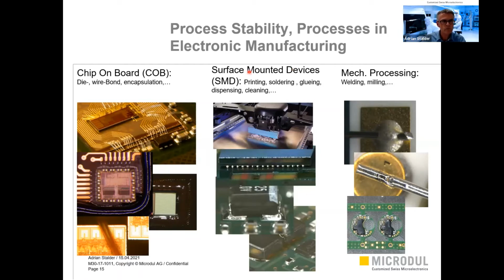In the middle one is a typical standard SMD process. That's a little bit more simple. Therefore, we have various dimensions, various chip sizes, various capacitor and resistor sizes. And we also do flip chips with the same process down to 100 micron. The third category is mechanical. So mechanical drilling, welding, milling. Here you see a picture of laser welding of contacts. That's mostly for our implants, the feedthroughs. They have some mechanical feedthroughs. That means a hermetically sealed interconnection between the inside electronics and the outside of the implant.